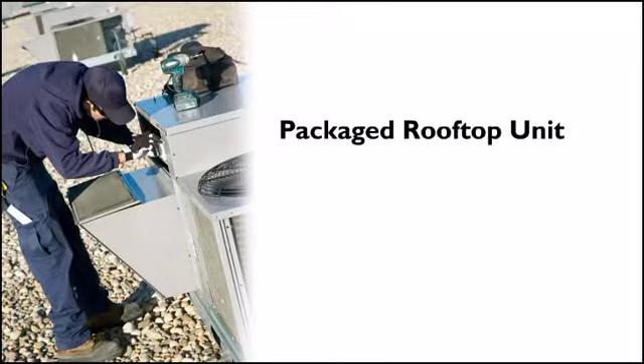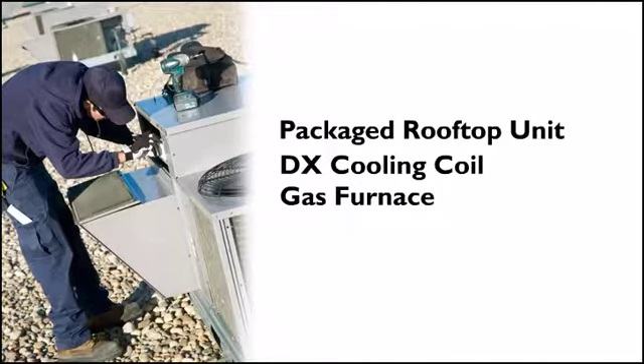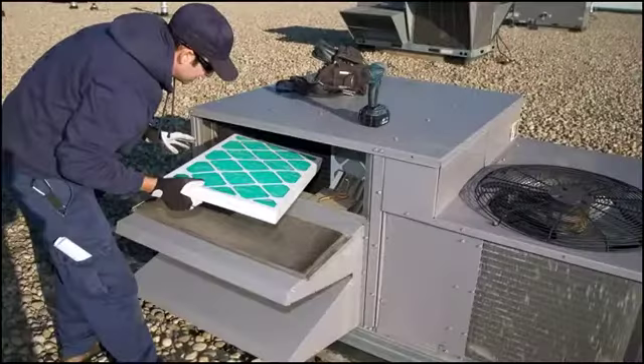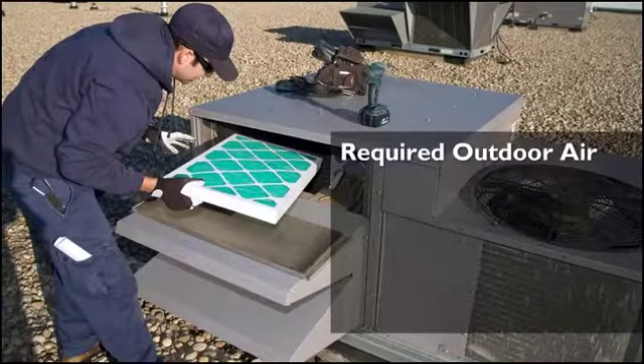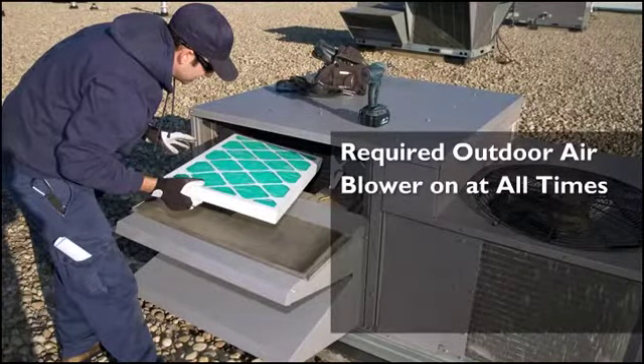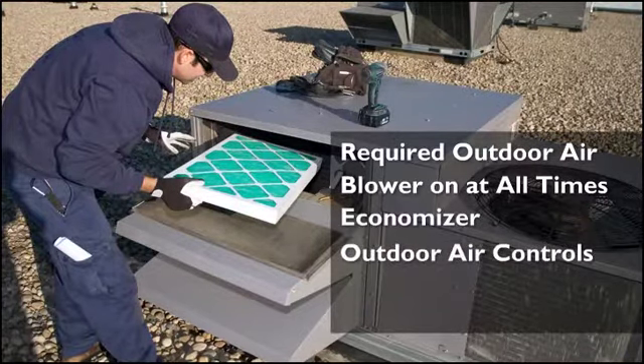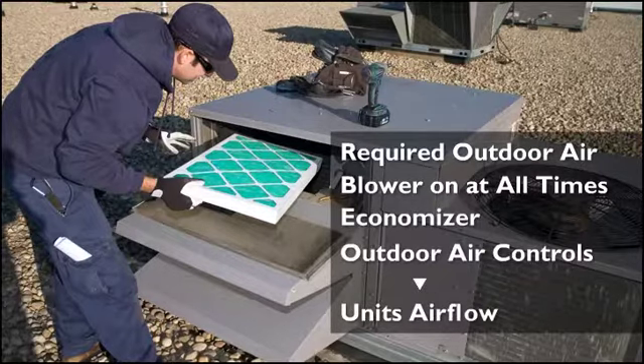The retail building system was a packaged rooftop unit, including a DX cooling coil and a gas furnace with a separate system for each zone. Each unit provided the required outdoor air, so the blower was on at all times when the zone was occupied. When the building required an economizer, the outdoor air controls were applied to the unit's airflow.